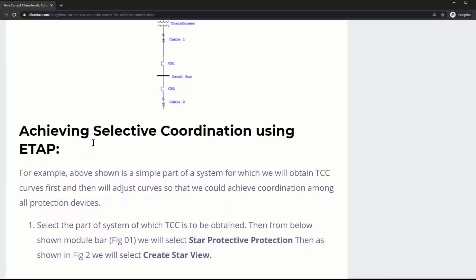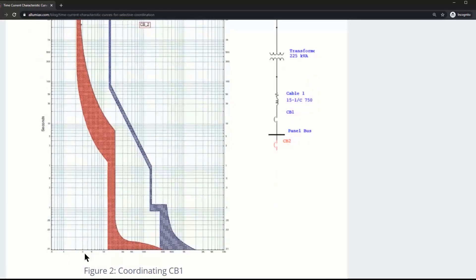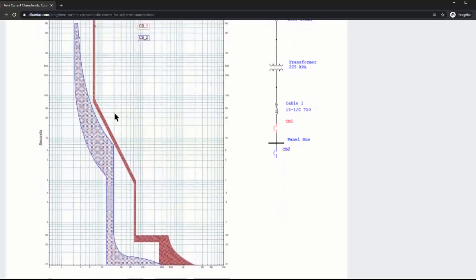Achieving selective coordination using ETAP: the downstream breaker is furthest to the left on the TCC curve because it will operate at the lowest amount of current. Current is on the x-axis — for example, 300 amps of current flowing would cause it to trip in perhaps 20 seconds. CB2 is the furthest downstream so we expect it on the left side, and CB1 is the topmost so we expect it on the right side, with no overlapping regions.